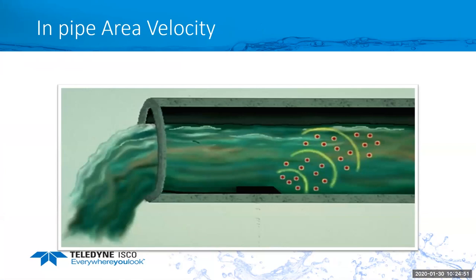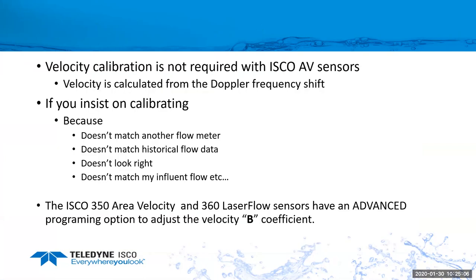Another example of that is we have our AV sensor in the pipe with the pressure transducer to read the depth of the water. It fires a 500 kilohertz signal that bounces off all the particles and air bubbles in the water to give us an average velocity from that frequency shift.